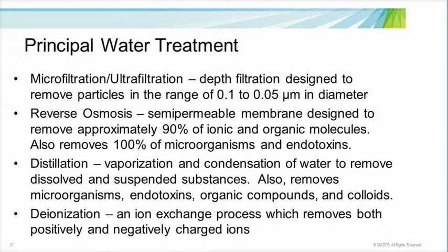Distillation is the process of phase change, or vaporizing and subsequent condensing of water, to remove dissolved and suspended substances. Distillation is extremely effective in removing microorganisms, endotoxins, organic compounds, and ionic impurities as well. Deionization is the process of removing ions via ion exchange. Effective deionization can remove 98% of both positively and negatively charged ions. In high-quality water systems, combinations of these treatment methods are common in system designs to meet the required need.